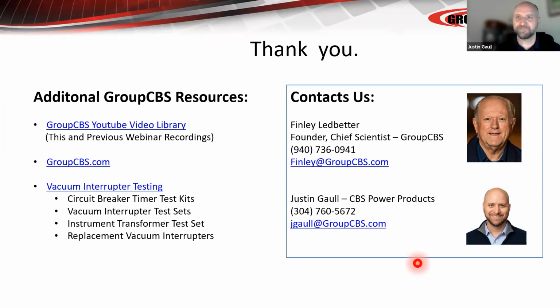That all goes back to lube, okay? If you've got a 30-year-old breaker that's got less than 1,000 operations on it and it's never been torn down and you've never had it relubricated, every 5 to 10 years that needed to happen. So chances are you have mixed lubrications of different generations that are crudding up. I can promise you you've got a problem, especially if it's a main breaker or on a critical circuit. I would be very cautious with a 30-year-old breaker that's never had any major maintenance.